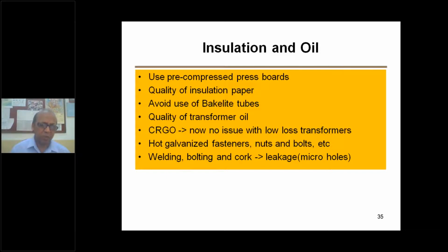Avoid the use of bakelite tubes. Bakelite tubes have poor strength, so wherever possible it is better to make your tubes from laminated wood rather than bakelite. Then, no doubt, quality of oil need not be discussed here; there are many platforms where it is discussed. CRGO earlier was the most important issue as far as the cost of the transformer is concerned. Now practically no issue with low loss transformers. When manufacturing a low loss transformer, you can't compromise on the quality of CRGO because you will not get the losses. If properly tested, nobody makes any adjustment with the CRGO.